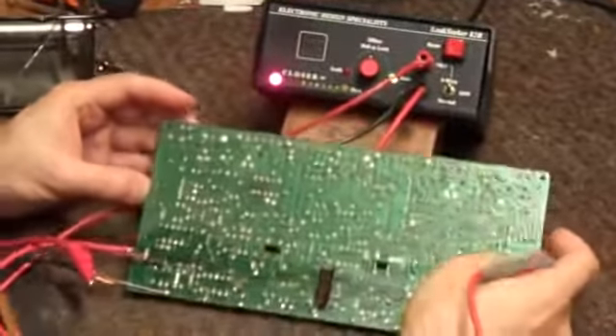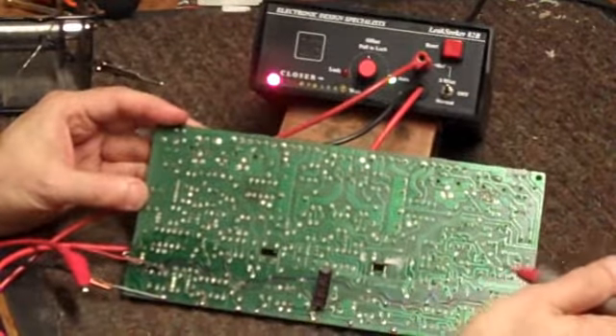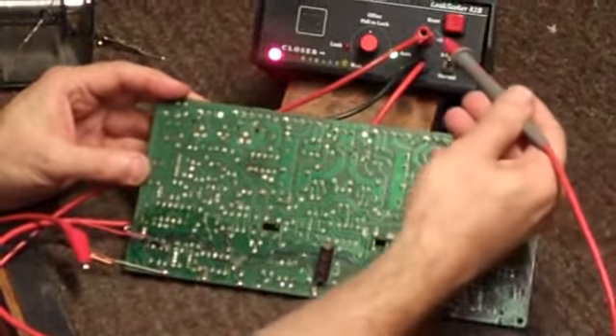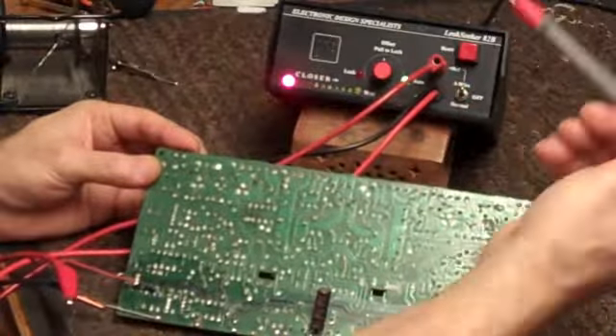So that's using the LeakSeeker in the 3-wire mode, where again it separates the special voltage and current signal coming out through the third probe and the sensing probe.